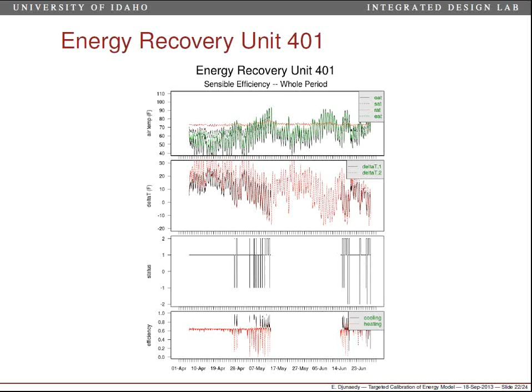Status 1 and status 2. 1 is heating mode, 2 is cooling mode, and it actually heats or cools the air. It works the same way. When it's in heating mode, the unit actually heats the air. When it's in cooling mode, it actually cools the air. But there is a -1 status, which means it's in the heating mode, but it's cooling the air. It happens, unless the logger is messed up. But it happens. There is this -1 status.